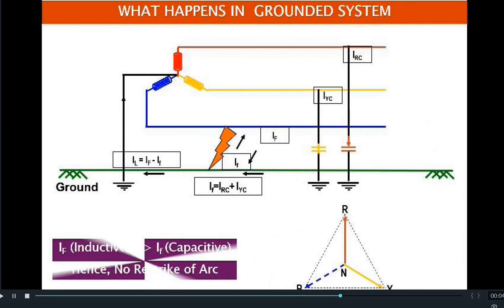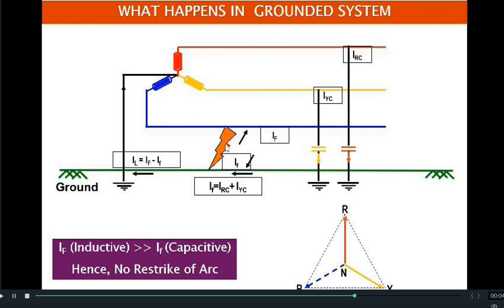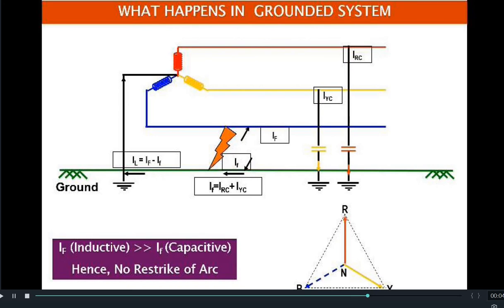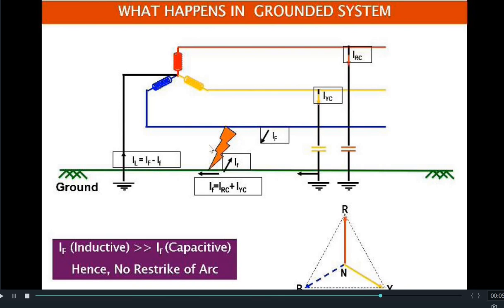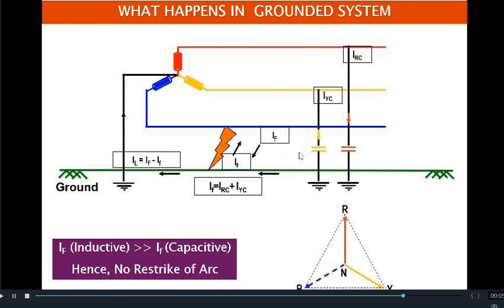If there is a fault in B phase in the grounded system, the potential of the ground is already made zero by connecting the neutral of the source to ground. So unlike the ungrounded system, the phase voltage does not shift from phase voltage to line-to-line voltage — it remains the same. Because of the B phase fault, there will be a fault current from B phase back to its source through the faulty path, which will be totally inductive. The capacitive currents IRC and IYC from the other two phases will still flow to the ground and towards their source through the fault path.